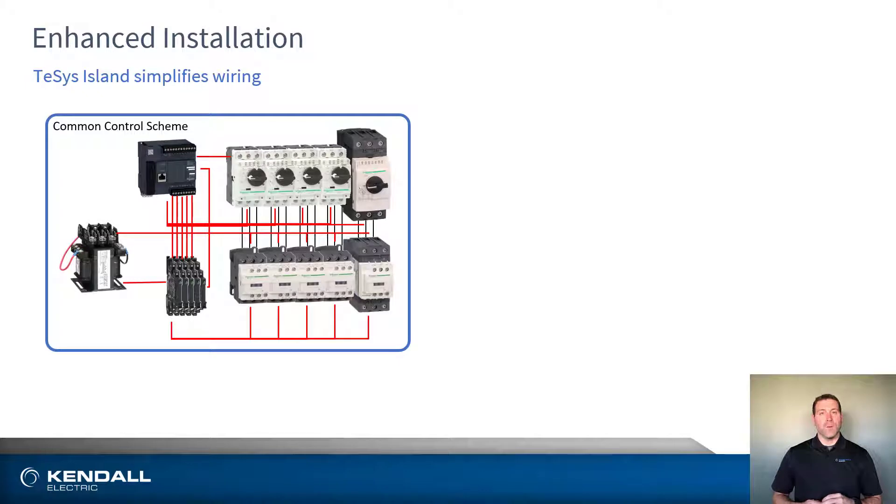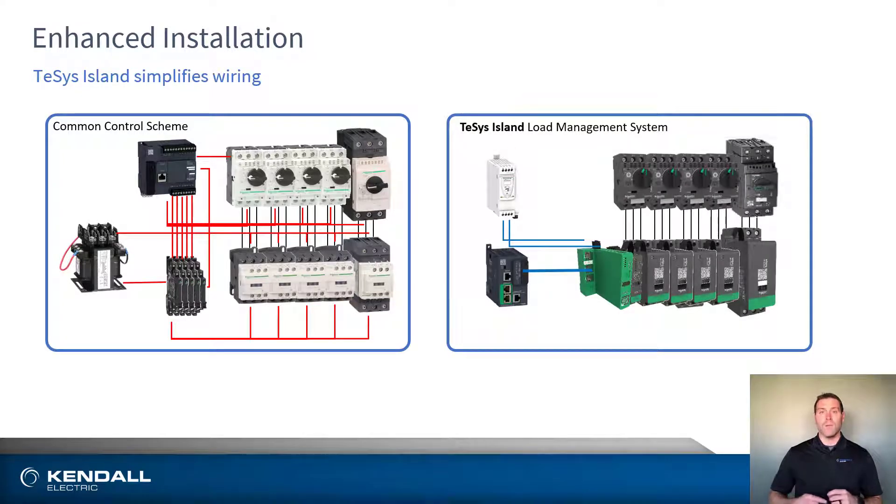Some of the first benefits experienced with the TeSys Island are the reduction in design time and installation through simplified wiring. Traditional motor control schemes require additional hardware and multiple wire connections between the PLC and motor control to accommodate the required IO necessary to operate the system. Whereas the TeSys Island only requires one ethernet connection to the island bus coupler to handle all of the startup, monitoring, and feedback.